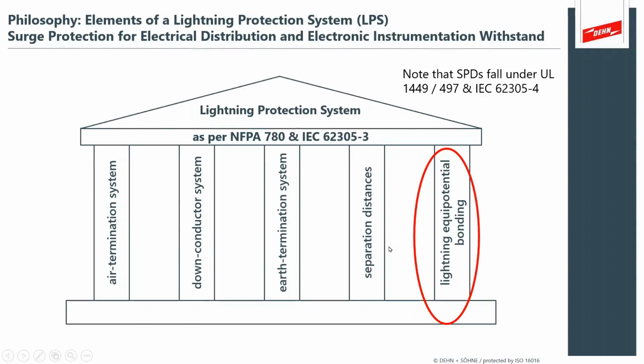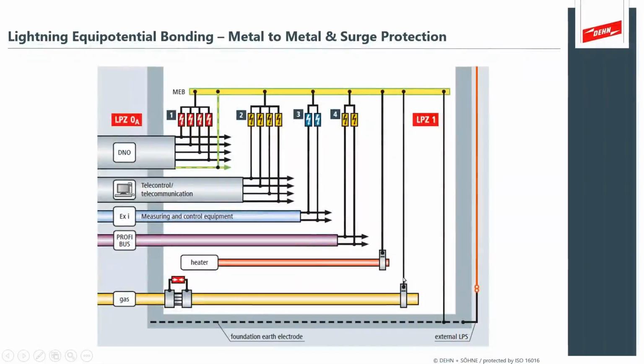Okay, so that is essentially bonding metal to your bus bar. Bond that stuff. That is the number one thing you can do to help your systems: to have a clean master ground bar and direct lines. Everything's connected directly to the master bar. The master bar connects directly to the earthing system, with short, straight leads, big gauge conductors, and clean connections.